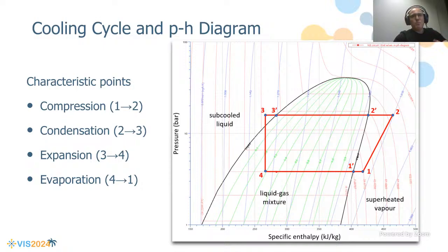Typically, when designing a cooling system, engineers do not specify these points directly when describing the desired cooling cycle characteristics. They specify low and high pressures and subcooling and superheating temperatures of the cycle instead, and the characteristic points can then be calculated from these values.